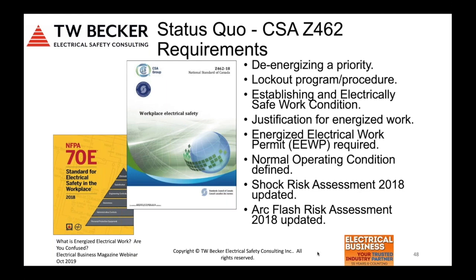Justification for energized electrical work is required. The energized electrical work permit requirement is quite clear in my opinion, but what I see in industry, it is not clear. I see a lot of, again, misinformation about the energized electrical work permit. Normal operating condition is defined as well. And again, we have the shock risk assessment and the arc flash risk assessment in the 2018 editions, which are both true risk assessments requiring 3 steps. Again, identify the hazard, potential injury or damage to health, and the likelihood of occurrence determined. Determine what risk control methods are required to reduce risk.